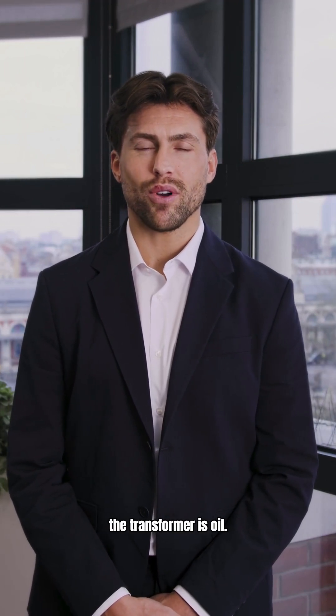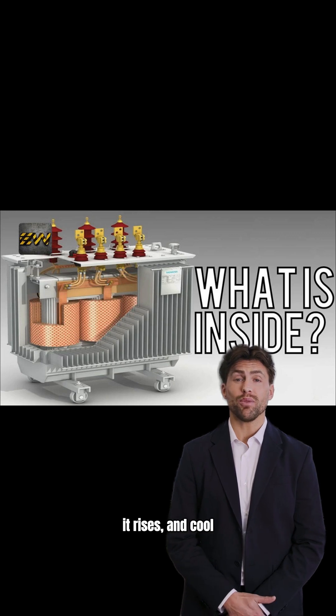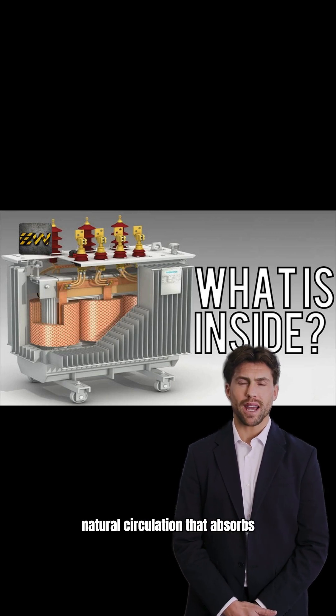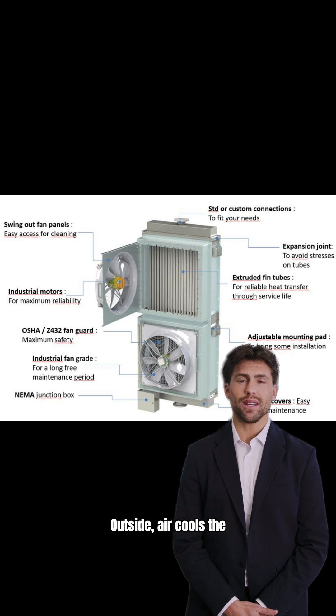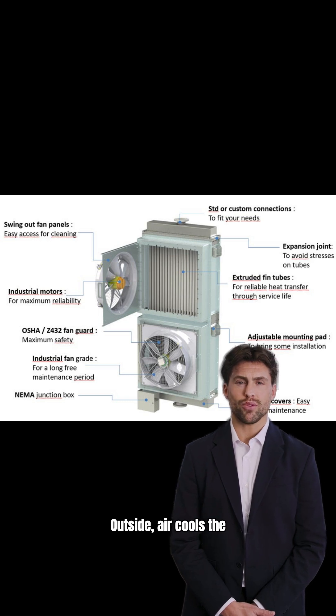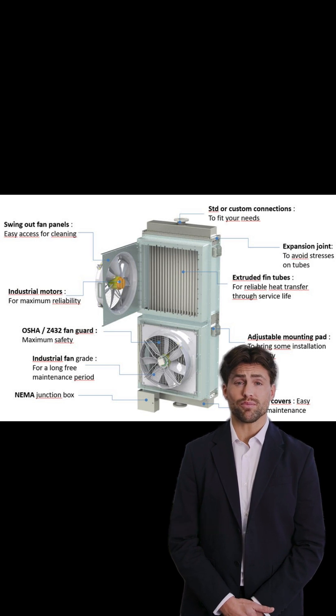Now it gets interesting. With Oil Natural Air Natural, or ONAN, inside the transformer is oil. As the oil heats, it rises, and cool oil falls, creating a natural circulation that absorbs heat. Outside, air cools the radiator fins. This is the most commonly used method, known for being reliable and low cost.